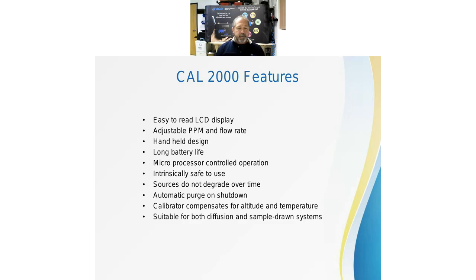Now this Cal 2000 instrument, again, is microprocessor controlled. It's got an internal mass flow sensor. The keys to generating gas on demand, as we're talking about in the seminar today, is you've got to have the flow rate that you blend the gas with right, and you have to have the current passing through the generating cell correct. So this instrument has an internal mass flow sensor so that it adjusts for air density. So it doesn't matter if it's cold or hot, or if you're up on top of a mountain or at sea level. The instrument knows what the density of the air is and compensates to make the calibration gas exactly what it's supposed to be.